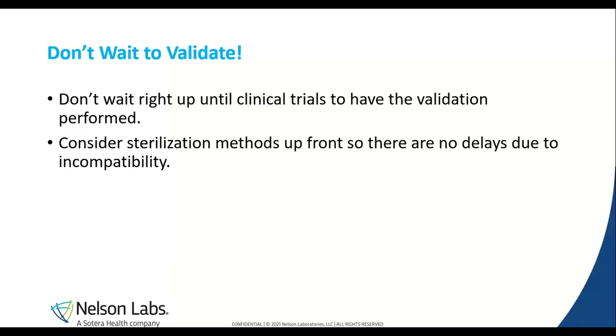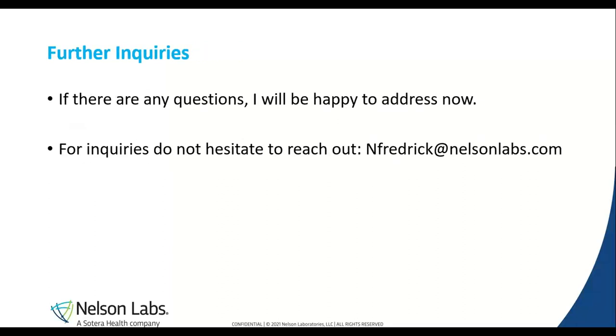One of my main points I would also like to convey is: don't wait to validate. If at any point during manufacturing the company decides to use a higher pressure or flow rate, or even a longer filtration time, a new validation will be needed in order to reflect these parameters. We have had instances where we run validations, and right as the product was about to be released for clinical trials, it failed the compatibility — meaning that it was deteriorating the filter and the filter essentially wasn't filtering the drug product; it was just acting as a tube allowing the product to go through. This could have been avoided if the compatibility was done sooner. For our Level 2 testing, we completely comply with PDA Technical Report 26 as well as FDA guidance documents. Nelson's product is the final report for all these tests, and we make sure that they comply with the various regulatory bodies. While all these tests are performed on a regular basis, we are also very flexible for R&D work regarding filters.